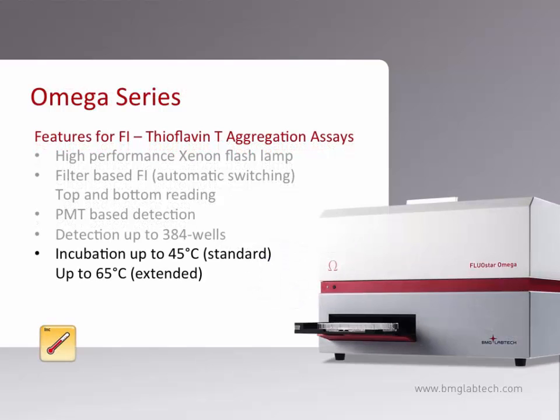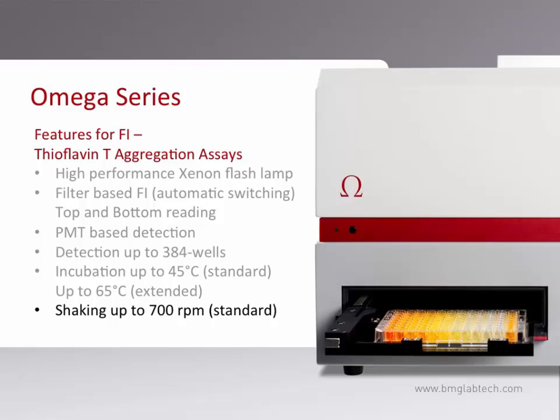The final basic need for performing thioflavin T assays is achieved in the Omega with a photomultiplier tube for sensitive detection of emission light. The ability to control temperature appears to be quite important in the RT-QUIC assay, and BMG has standard temperature regulation up to 45 degrees Celsius in all our readers, or you can choose optional extended incubation up to 65 degrees. Another important factor in successful RT-QUIC assays is robust shaking, and the transport system of the Omega appears quite well suited to this task.